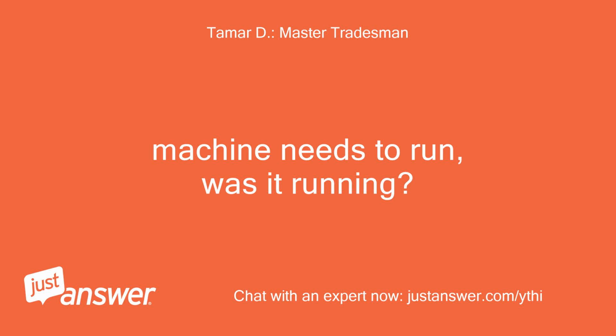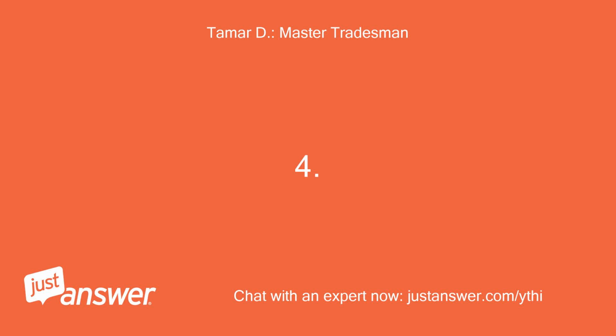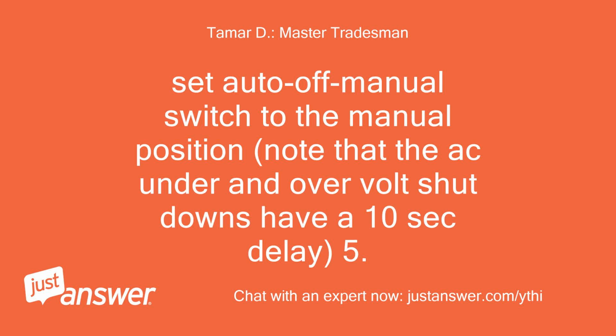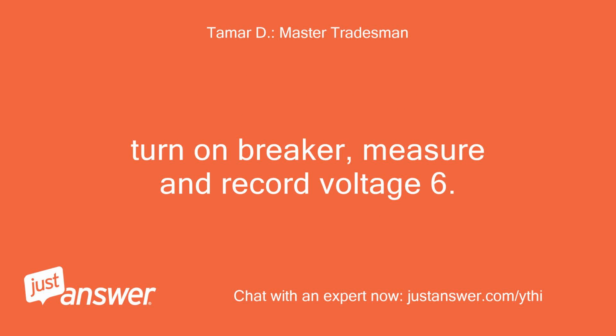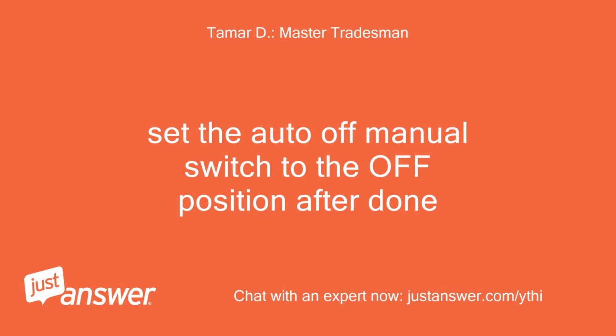Machine needs to run. Was it running? 4. Set the auto off manual switch to the manual position. Note that the AC under and over volt shutdowns have a 10 second delay. 5. Turn on the breaker, measure and record voltage. 6. Set the auto off manual switch to the off position after done.